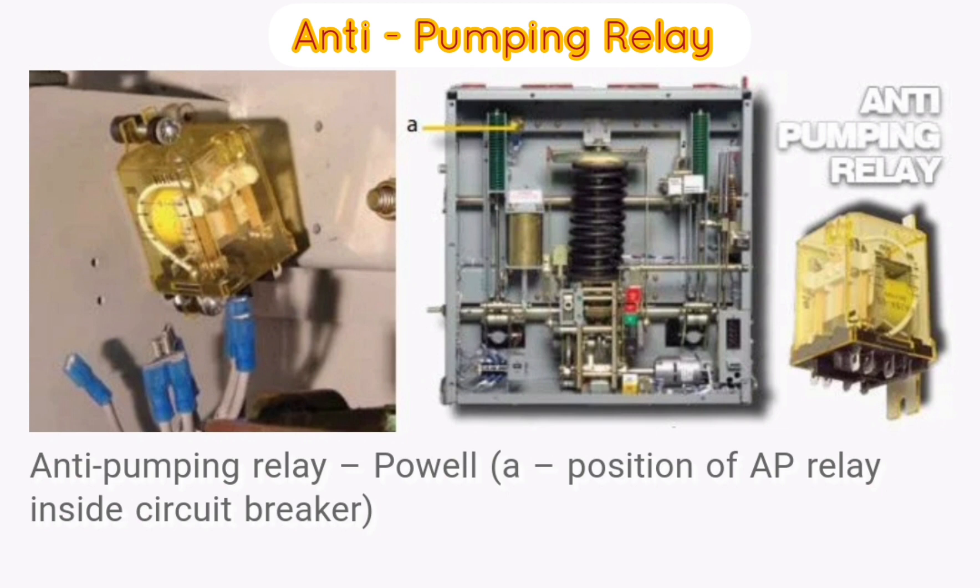The anti-pumping relay is important when the TNC (trip neutral close) switch and the circuit breaker closing circuit releases continuous circuit breaker close commands to the closing coil. The anti-pumping relay prevents this unwanted closing of the circuit breaker that may cause a safety hazard or equipment failure.